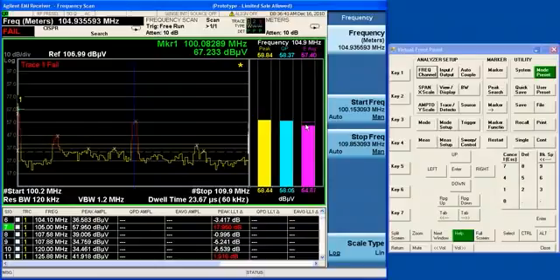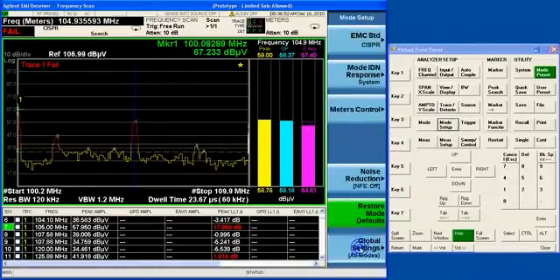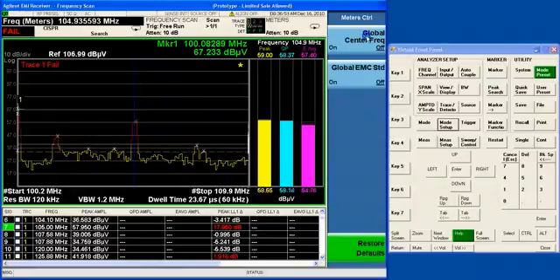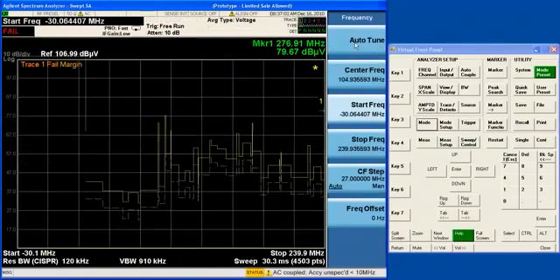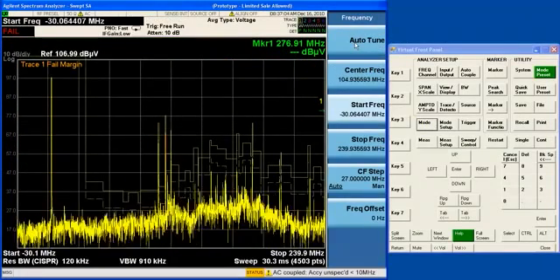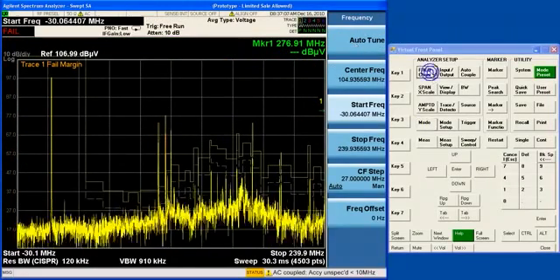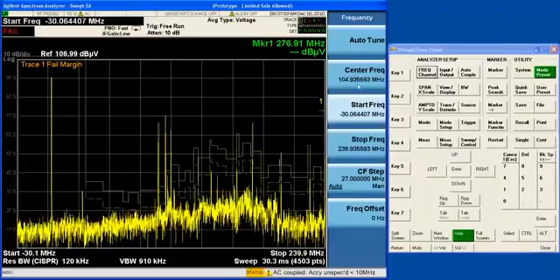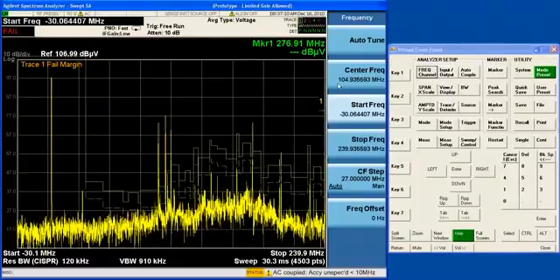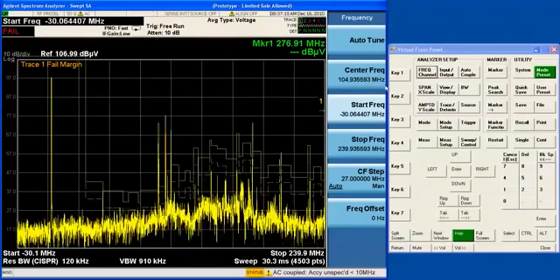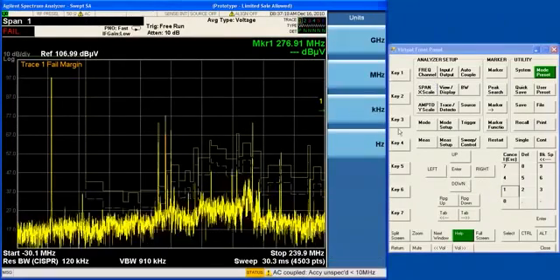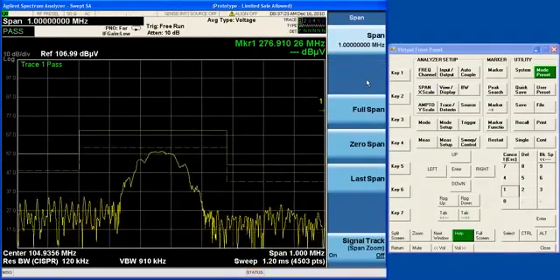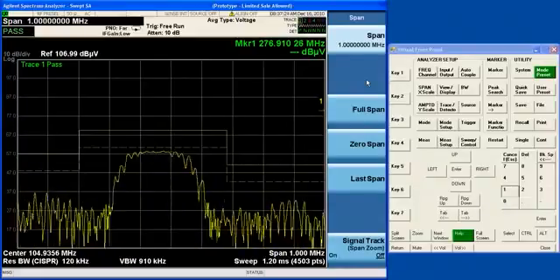Now I can actually do a meters to signal and replace this signal with the updated meter frequency. But another thing you can do with the X series is I can go to the spectrum analyzer measurement and get a look at this signal in real time. If you go to mode setup and set your global settings so that global center frequency is turned on, now if I switch modes back to the spectrum analyzer, I'll be at that same frequency. You can see that the center frequency is the same as the meter frequency was when I left the EMI receiver application. And so if I set my span to like a megahertz, now I can see the FM station in question.